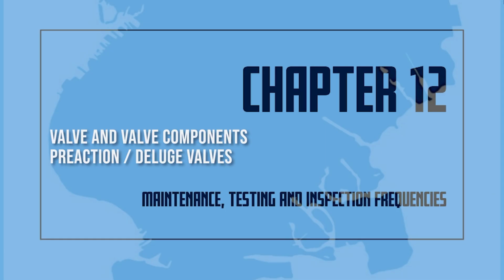Interior. The interior of the valve and the condition of detection devices shall be inspected annually when the trip test is conducted. Internal inspection of valves that can be reset without removal of a faceplate shall be permitted to be conducted every 5 years. Strainers, filters, restricted orifices, and diaphragm chambers shall be inspected internally every 5 years, unless tests indicate a greater frequency is necessary.